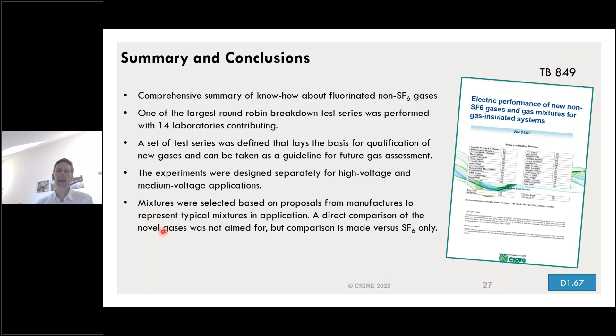Despite the extreme care that we have taken, creating reproducibility within one lab and between two labs is relatively difficult and was not always possible to achieve, to our surprise sometimes even for SF6. So dielectric testing is an art, and not always are all the influencing parameters known to us. Both mixtures, the C4 and the C5 mixture, show principally the same behavior as SF6. They are self-restoring and the breakdown strengths are quite similar.